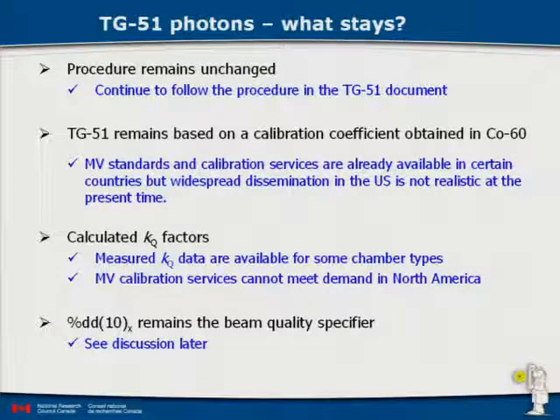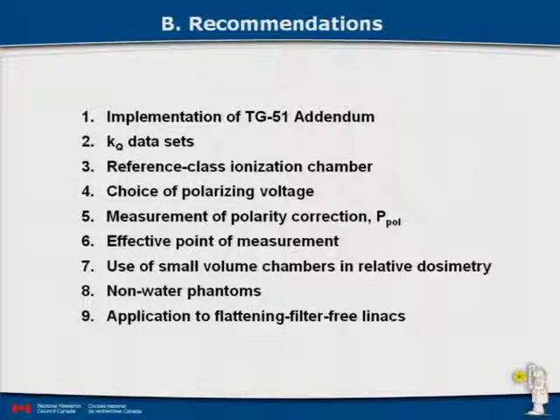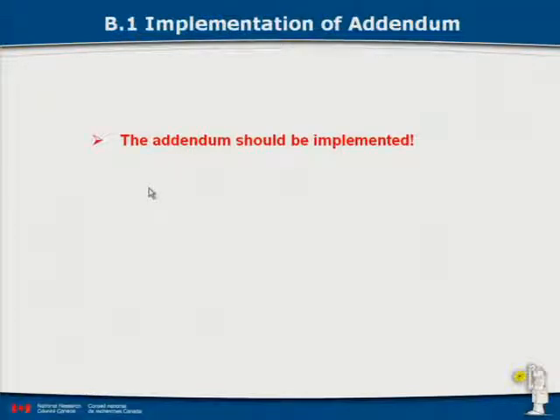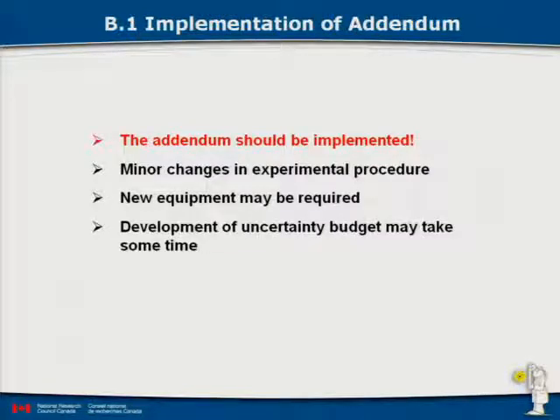The recommendations for implementation in the new addendum cover: KQ data sets, definition of a reference class ionization chamber, recommendations about polarizing voltage and polarity, effective point of measurement, small chambers, non-water phantoms, and flattening filter-free linacs. The basic guidance is you should implement the addendum when it's out. The good news is the changes are minor, so the effort required should be fairly straightforward. Some new equipment may be required because of other recommendations. The uncertainty budget may take some time, but the actual procedure will remain very similar in how long it takes to implement annually.